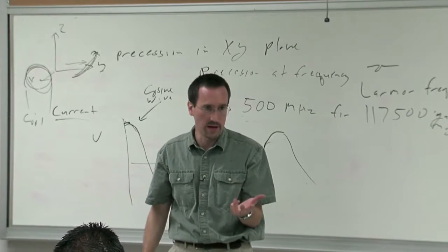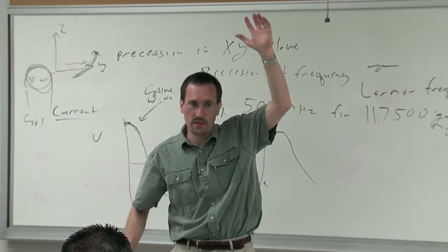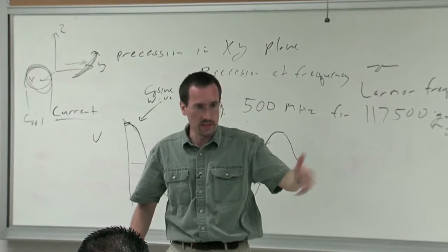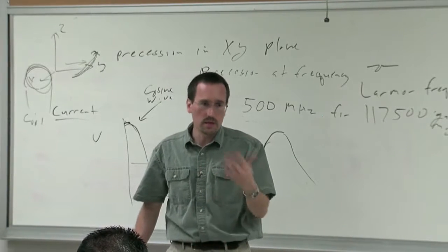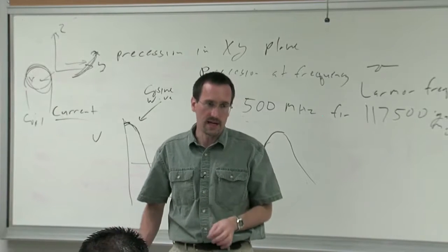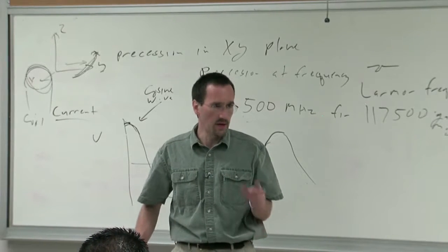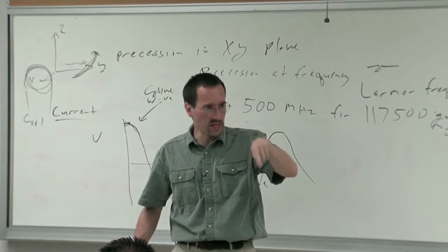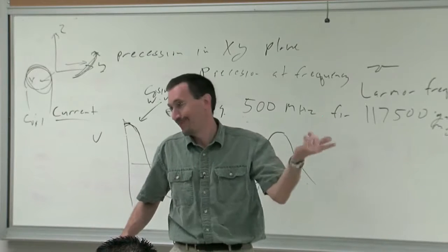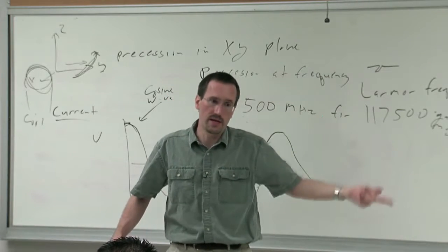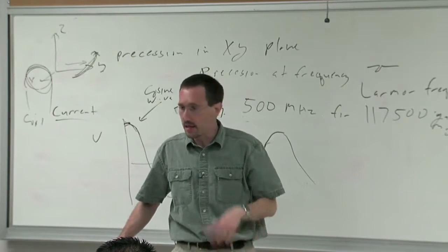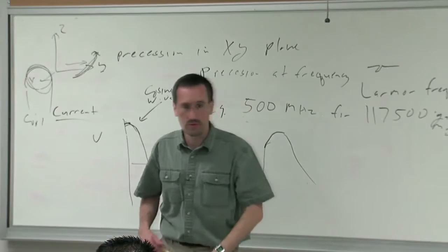So for those of you who've run a spectrometer, how many of you have run an NMR spectrometer? And you do number of scans equal to 4 or 8 or 16, that's no accident, because we are actually doing what's called phase cycling, which means in order to cancel out artifacts, we do a set of 4 experiments or 8 experiments. So you first do a positive X pulse, for example, then a negative X pulse, then a positive Y pulse, then a negative Y pulse. And then we average them all together, and that reduces artifacts.